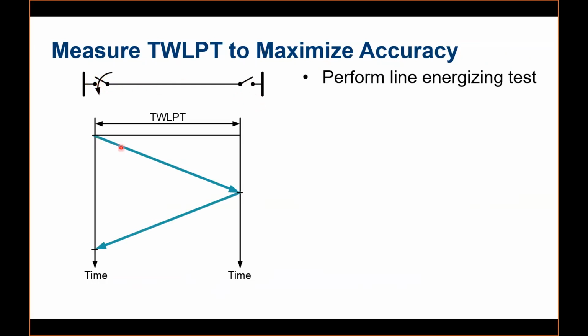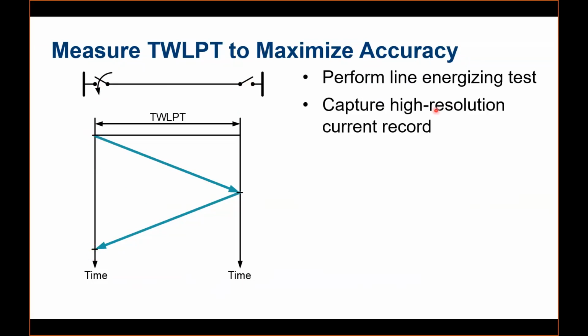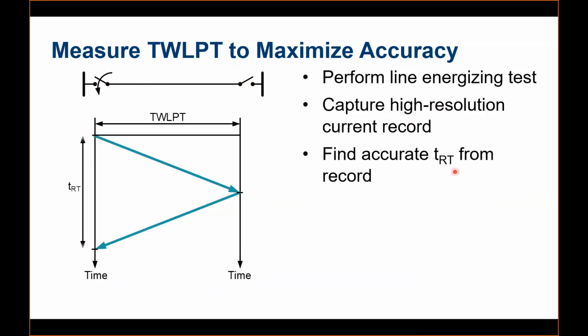That traveling wave will travel to the remote end, and it will be bounced back. There's a property of reflection for all traveling waves because there is a change in impedance. So if that end is open, the traveling wave will be reflected from this end and come back. Because we have a very precise time measurement on this relay, it can measure the time when the wave is generated over here and when it comes back. So if we have the information on these two times, from the relay event records, we can capture the round trip delay.